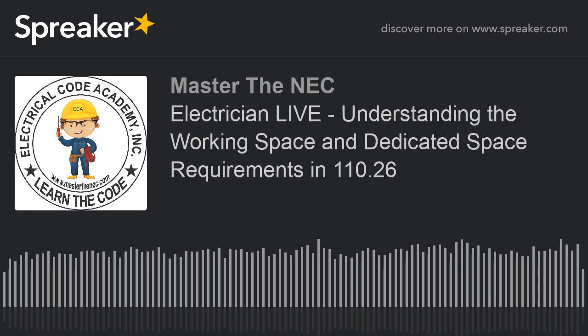Okay? Now we get into C. This is similar to what we just talked about for indoors for the dedicated equipment space, but this is very specific. And it says, the dedicated equipment space, the space equal to the width and depth of the equipment and extending from grade to at least 6 feet above the equipment shall be dedicated to the electrical installation. No piping or other equipment foreign to the electrical installation shall be located in this zone. Okay? And then, of course, an exception was added in the 2020 that said structural overhangs or roof extensions shall be permitted in this zone. Again, not going to be a problem. They're inherent to the construction. They could be in that zone.